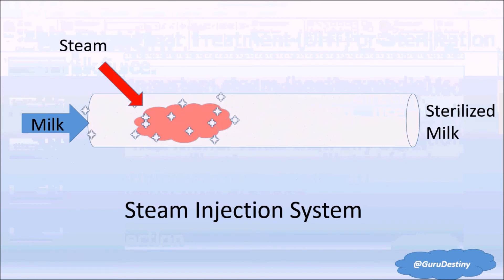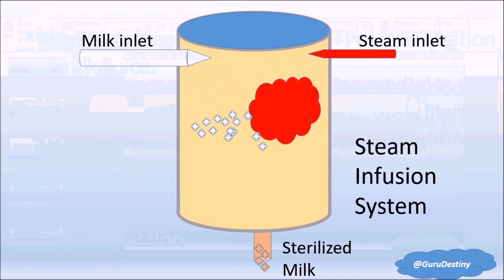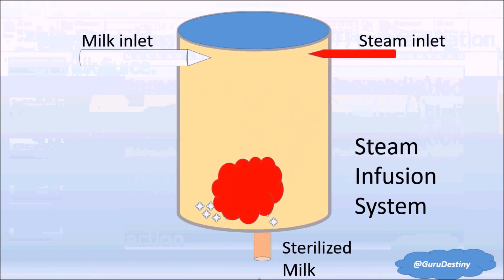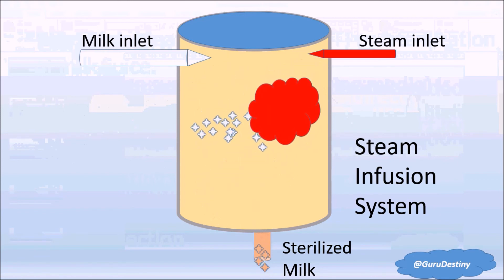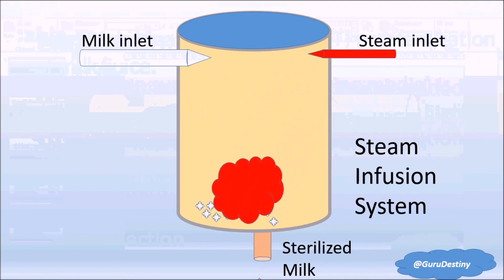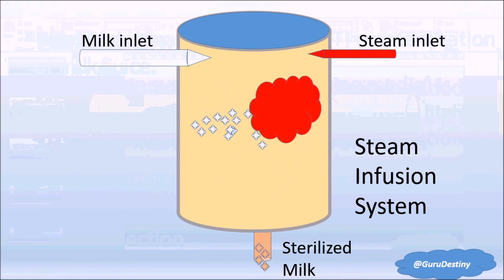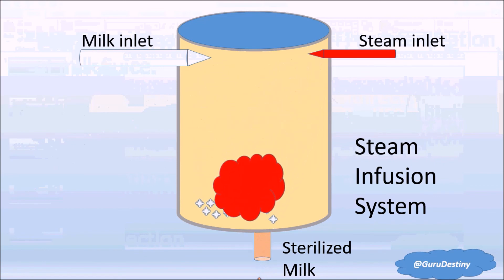In the steam infusion system, the product is sprayed into a large chamber, and so is the steam in the same chamber. The product absorbs heat and water from the steam. In the next section, we remove the water and heat to cool the product. The cooled product is the final product, and with no need for refrigeration, it is packed aseptically.